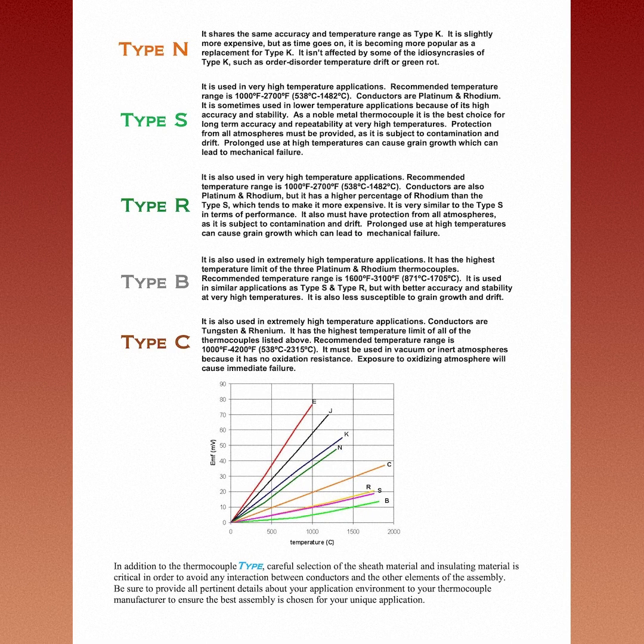Type S is used in very high temperature applications. Recommended temperature range is 1000 to 2700 degrees F or 538 to 1482 degrees C. Conductors are platinum and rhodium. It is sometimes used in lower temperature applications because of its high accuracy and stability. As a noble metal thermocouple, it is the best choice for long-term accuracy and repeatability at very high temperatures. Protection from all atmospheres must be provided, as it is subject to contamination and drift. Prolonged use at high temperatures can cause grain growth, which can lead to mechanical failure.